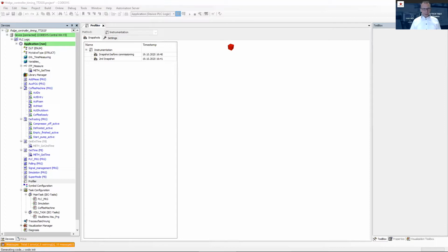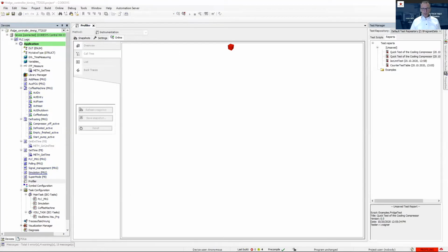So there's a question in the meantime. My question was how I determine in my POU programmatically for the first scan to run a certain piece of code, similar to other competition like Schneider or Rockwell. Yeah, if you do it the manual way, you can do that within the application, have any counter and do it like that. You can check using a special counter, which just runs through the first time the code was executed and then set it to a certain value, and then check whether it was executed before and skip it in case you do not want to measure it anymore. Or you just take the profiler, where this is done automatically.